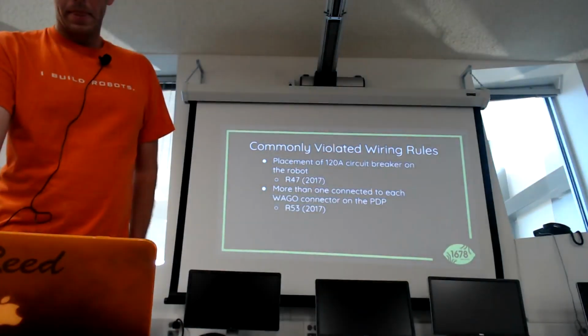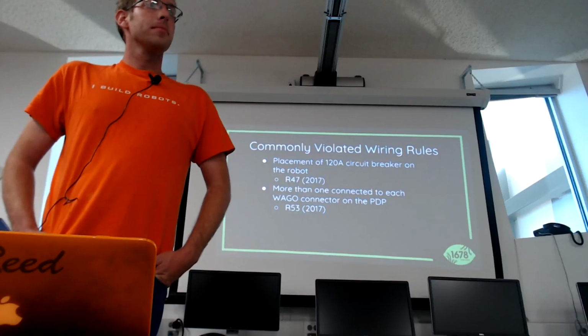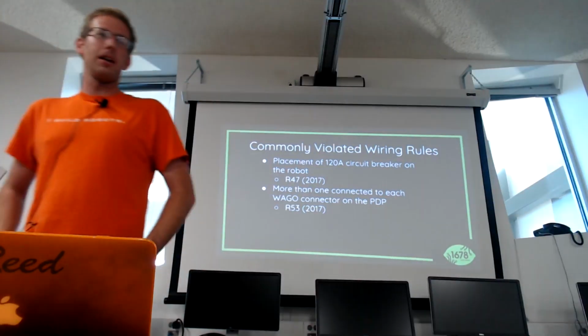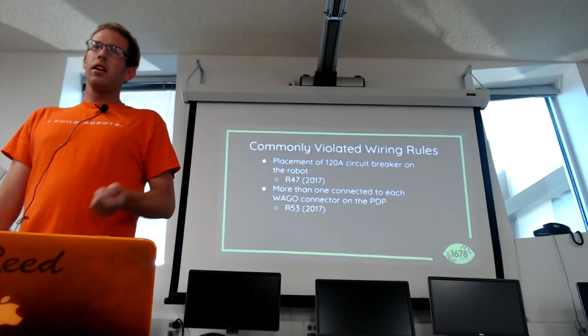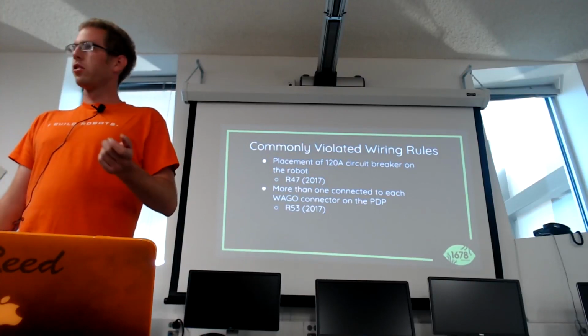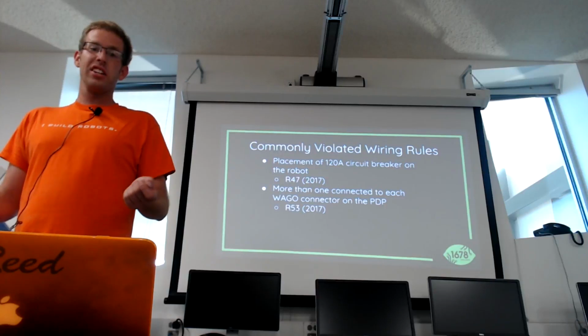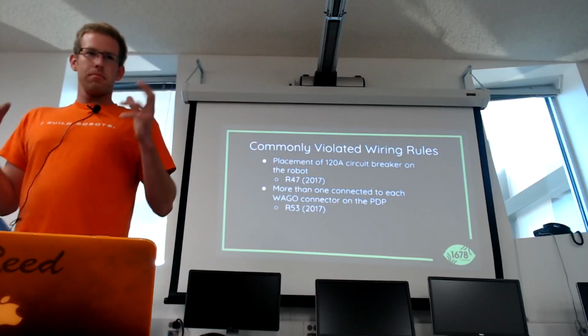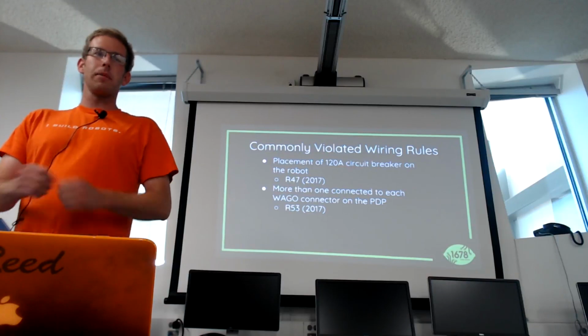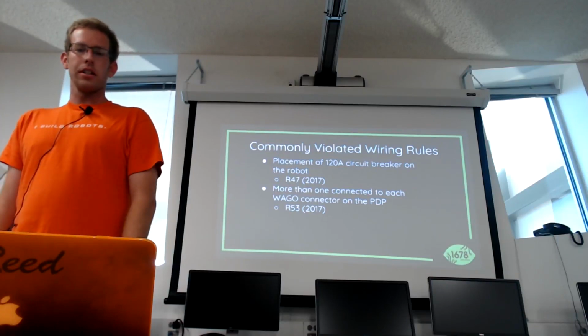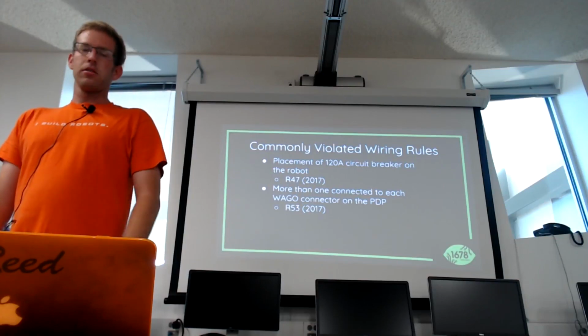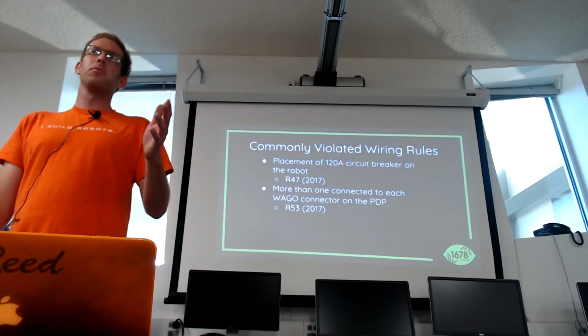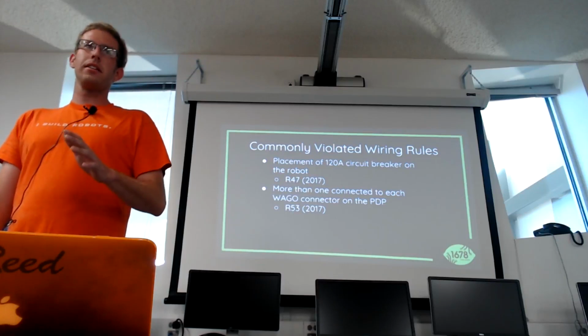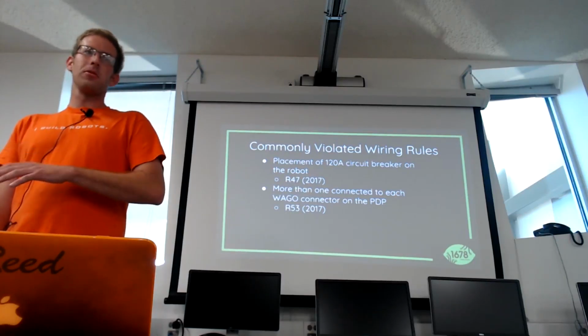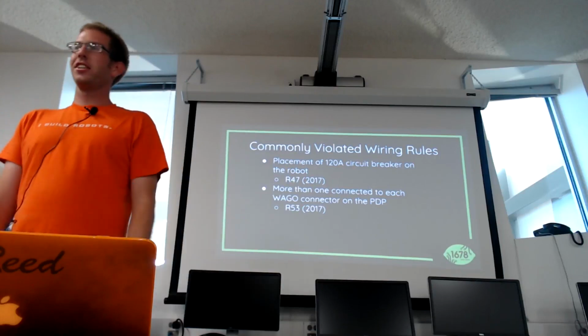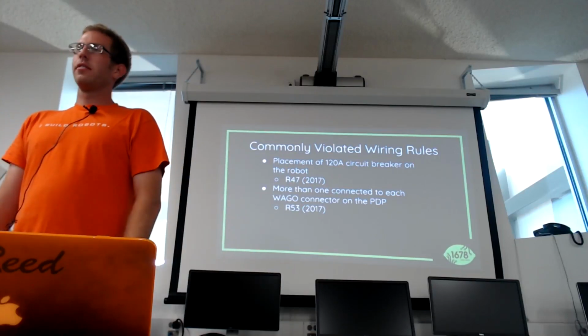To your point, it's okay to oversize - yeah, so we'll oversize sometimes. For the 40 amp circuits, we'll run 10 gauge to most high current drawing items, like our drive train, to get as much as possible out of that, so we're not heating up that wire, getting more resistance, causing issues. Sometimes we'll go back and change some gauges of wire so we can make weight when we're close to the limit.